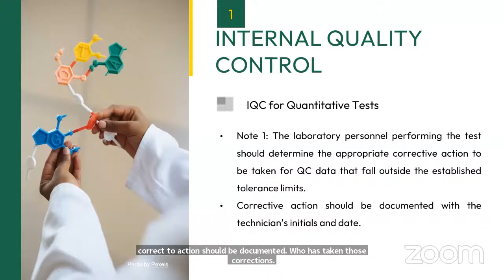There is another note: for tests for which quality control is not available, or when running control is not viable due to low volume of tests, the laboratory should apply alternate quality control techniques. These are alternate quality control techniques which should be used in the absence of quality control material. They include retesting of any randomly chosen specimen, replicate testing of a specimen by a different method, different machine and different persons where applicable, and correlation of the test results with other parameters. So these are the alternative additional quality control measures.